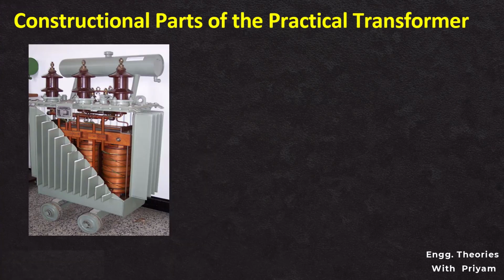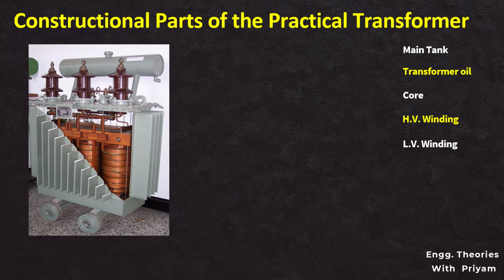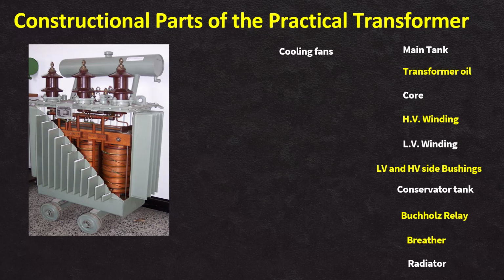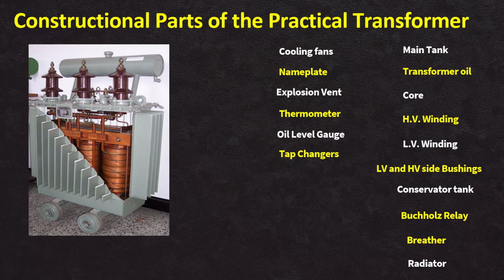In this lecture, we will get ourselves familiarized with the different components in a practical transformer. There are a lot of different components in a transformer, and it is difficult to list out all of those components, but the main components are main tank, transformer oil, core, HV winding and LV winding, HV and LV bushings, conservator tank, Buchholz relay, breather, radiator, cooling fans, nameplate, explosion vent, thermometer, oil level gauge, tap changer, wheel and lifting lugs, and also insulation. We will learn about the installation location of these components in the transformer, but the details of their workings will be discussed later.